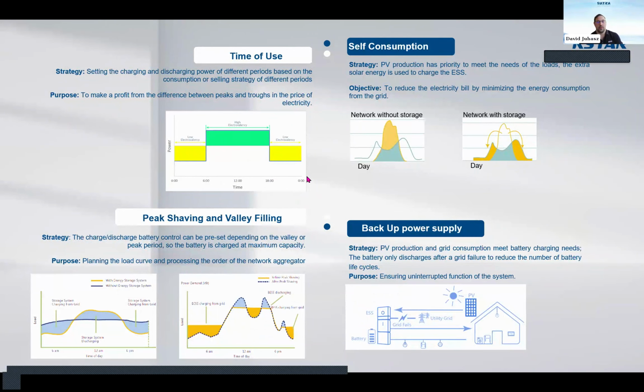Regarding the operating modes, it has 4 operating modes. The first is the time of use, where you can set the discharge and charge periods of the system according to the electricity price, and make some profit by charging the equipment when the prices are low, and discharging the equipment when the prices are high.